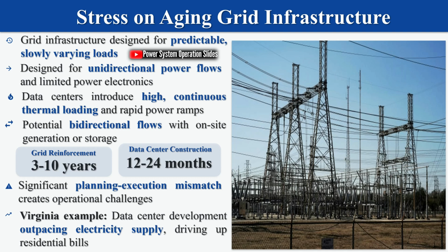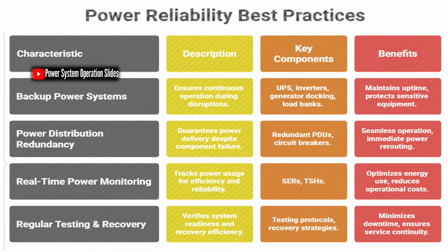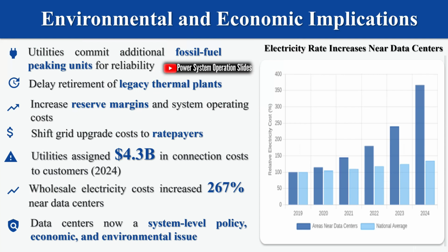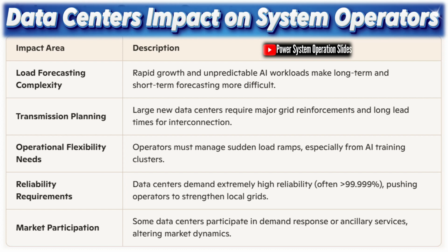Data centers also affect power quality through their reliance on power electronic interfaces, including switch-mode power supplies, uninterruptible power supplies, UPS, variable speed cooling drives, and rectifiers for DC bus architectures. These devices introduce harmonic distortion, degrading voltage waveform quality, and create low power factor, increasing reactive power demand. From a system operation perspective, poor power quality can increase system losses, cause misoperation of protection devices, and accelerate aging of transformers and capacitors. The stress on aging grid infrastructure represents another significant challenge.